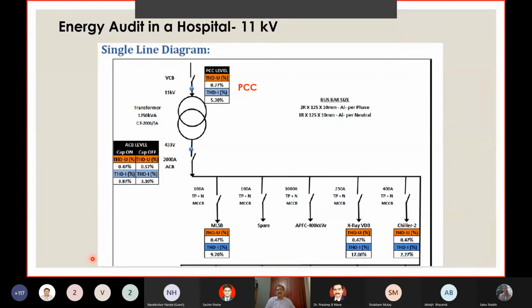Now I have taken the case of an 11 kV supply to a hospital in Chennai. I'll be using about 5-6 slides to bring out both the power quality as well as the power studies that we have done. So this is a simple one transformer with multiple load feeders. A simple SLD has been shown here. There are more feeders, but I have limited it for the purpose of the slide to a few feeders only, including an APFC of 400 kVAR installed.